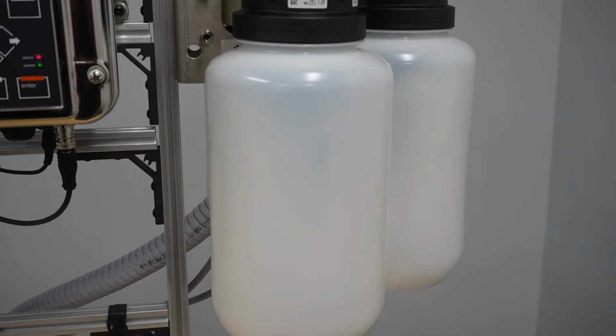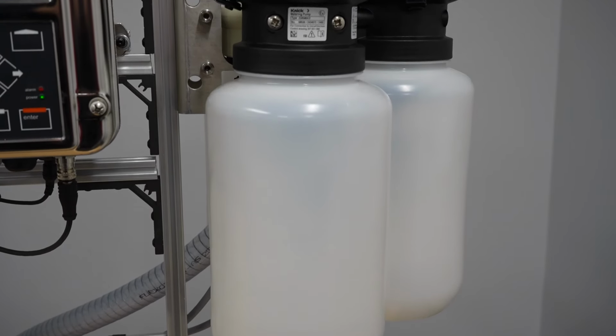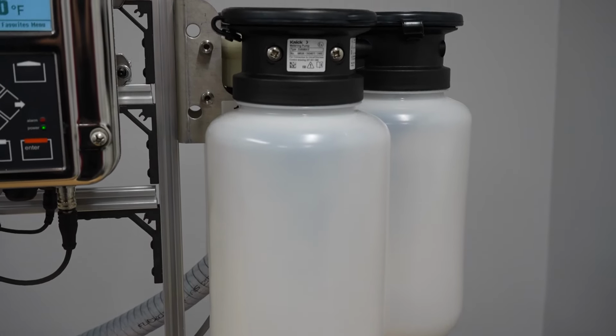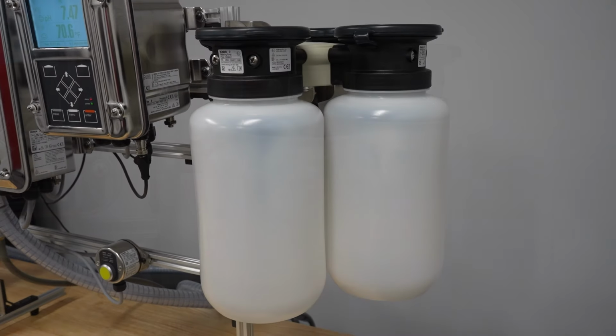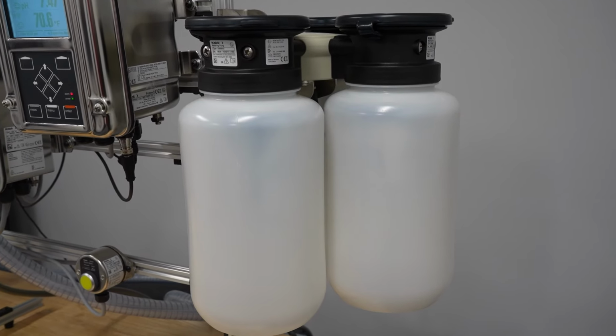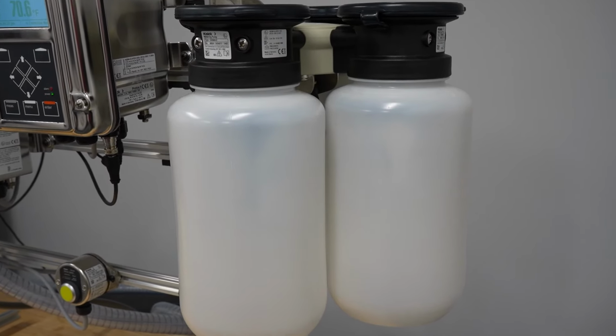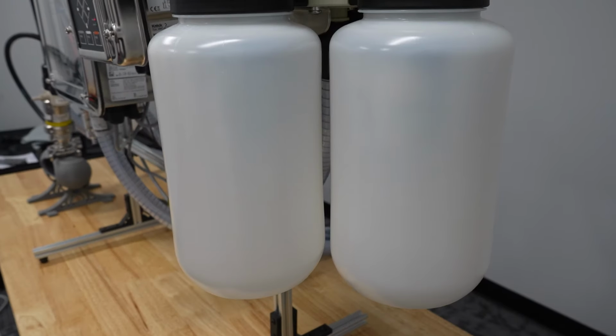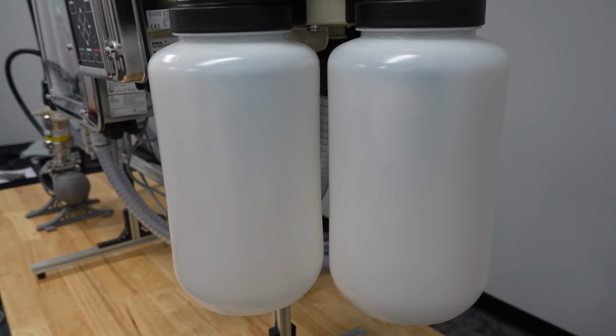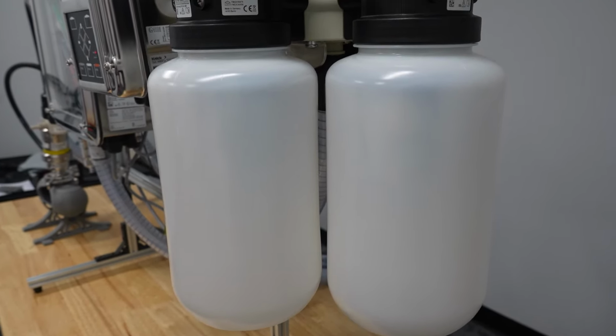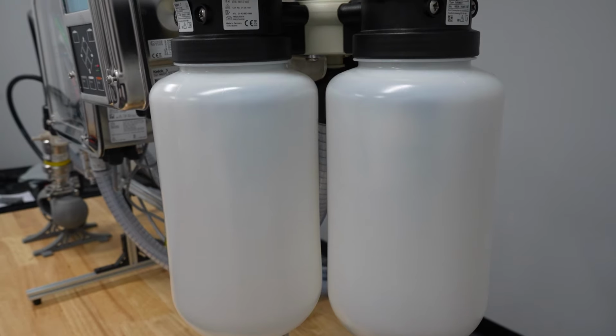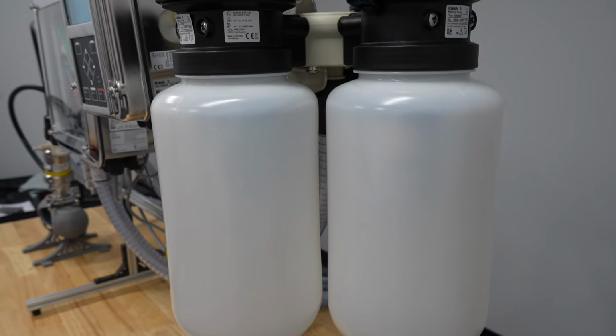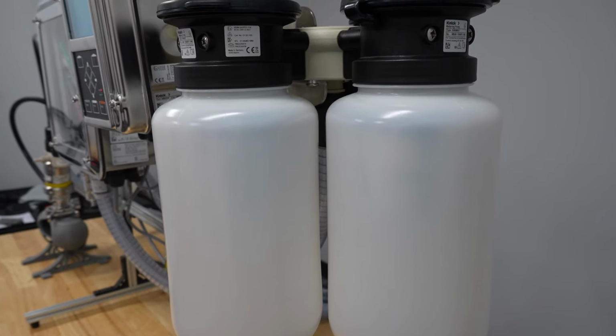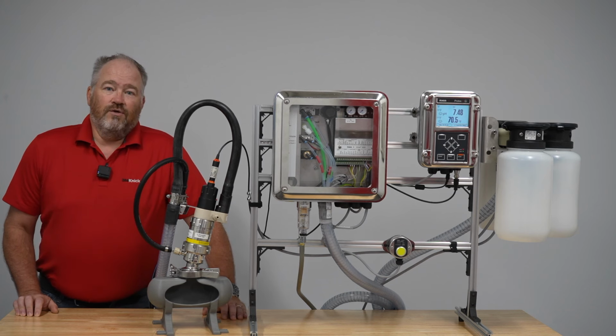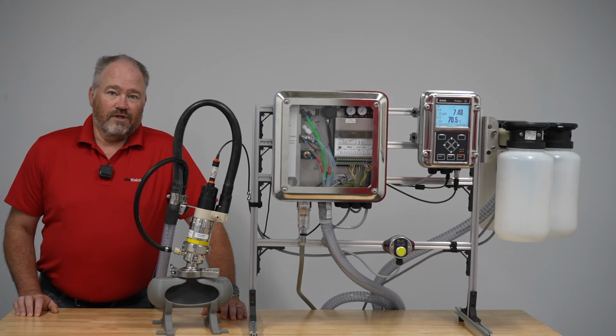To complete the system, we have onboard containers for the different calibration and cleaning solutions, which are used when a calibration or a cleaning program is running. The bottles have integrated level indication indicating when the system has 10 remaining calibrations or cleaning cycles. Typically, you have approximately 140 calibrations and cleanings with a full set of bottles. cCare can be used in a variety of industries and applications tailored to the customer's needs.